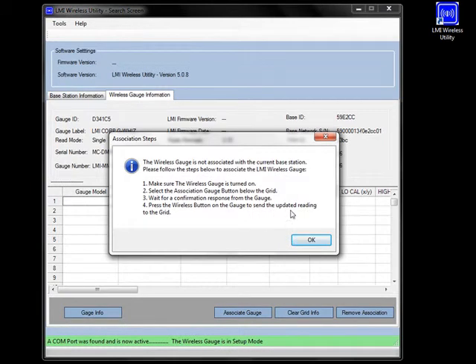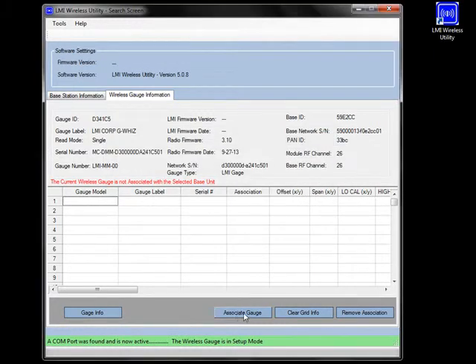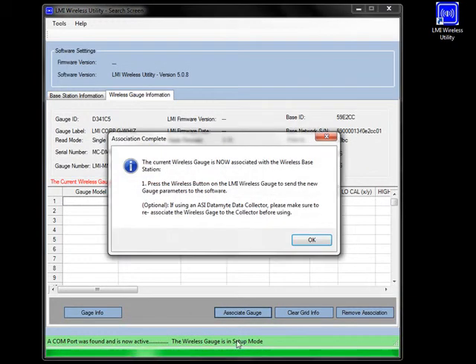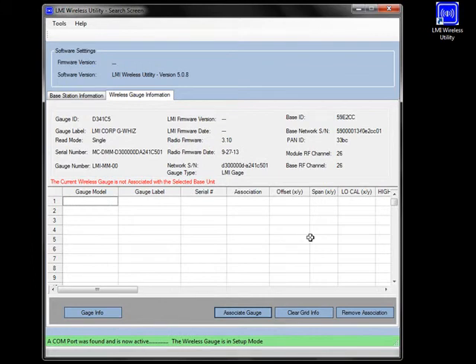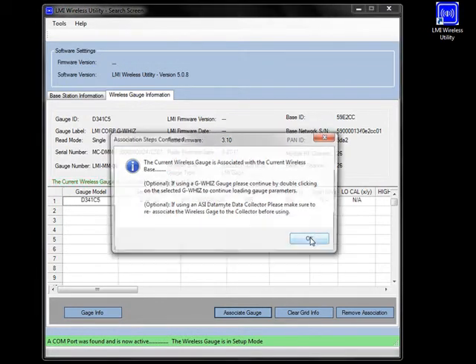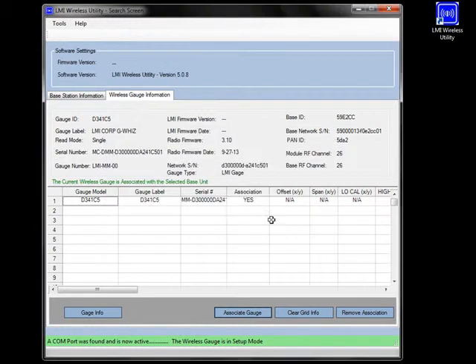So, with the gauge in setup mode, we're going to push the center button. And you'll see that the gauge is not associated on the little pop-up menu there that says the steps that you'll have to follow. Basically, what we're going to do is we're just going to click on the Associate Gauge button. We'll wait for this next pop-up to appear. We'll click on OK. And we're going to push the button on the gauge itself, the center button again. And if it's associated correctly, you'll see that the gauge ID will appear on the first line of the grid, which I'm circling right here.